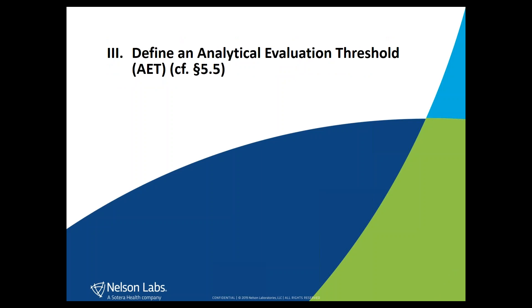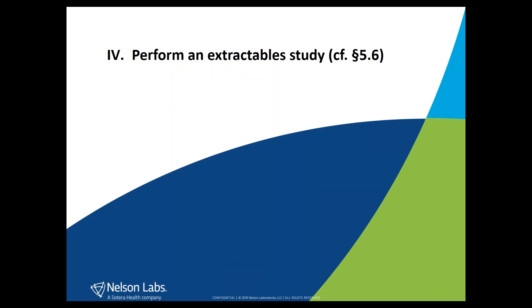Before proceeding to extractable testing, the guidelines emphasize that you will first need to define an analytical evaluation threshold, as described in paragraph 5.5 of the final draft. When looking at the wording 'analytical evaluation threshold,' it means it is a threshold to evaluate analytical results. We will dig into this AET concept later in this webinar and first explain how to set up an extractable study.